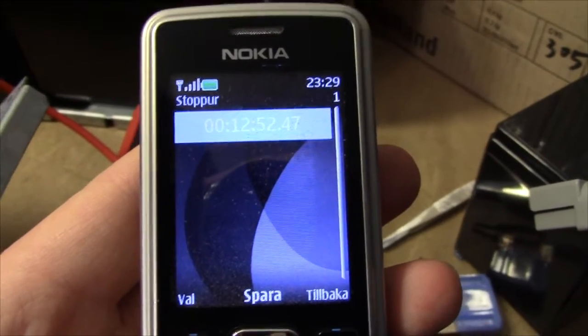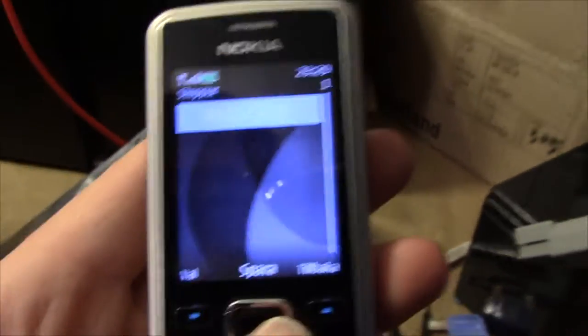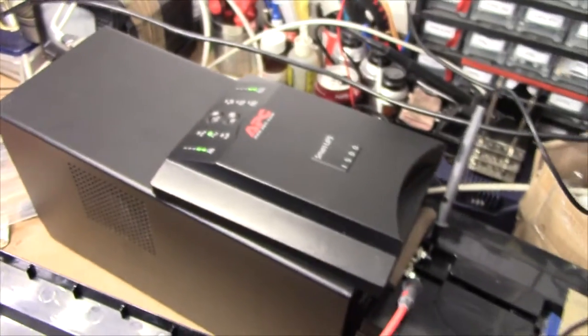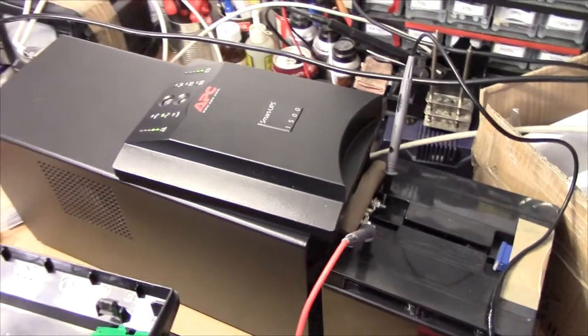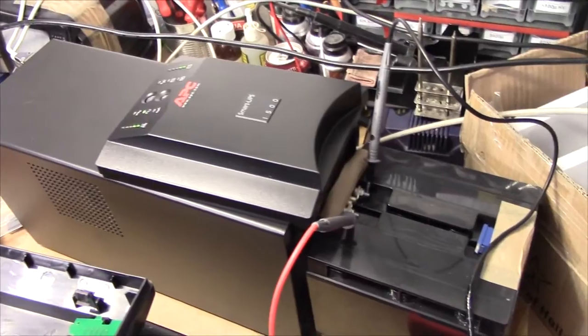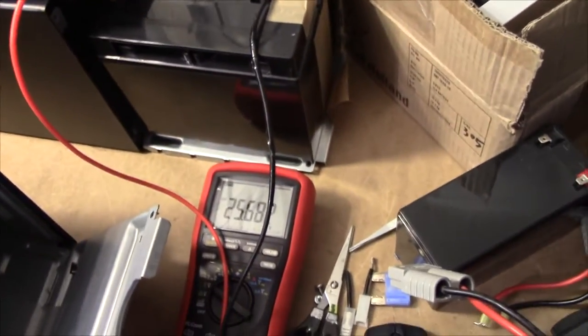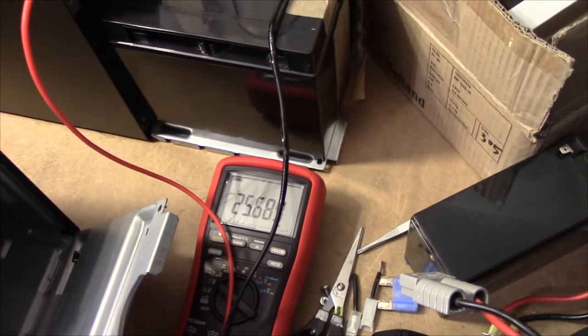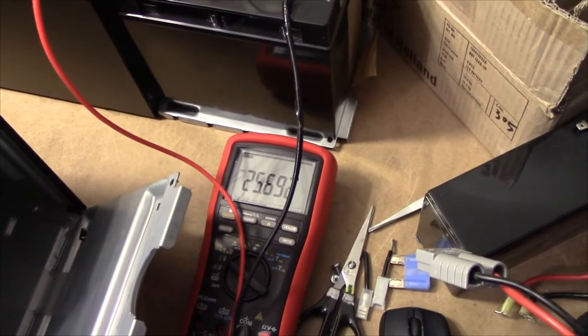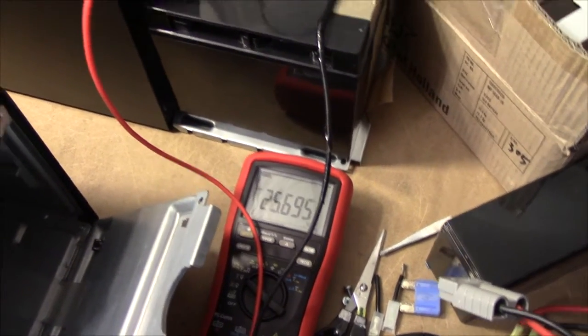Well, we just stopped calibrating at about 13 minutes, which doesn't really bode too well for this unit because it should run for considerably longer. The battery voltage didn't drop as low as it's supposed to.